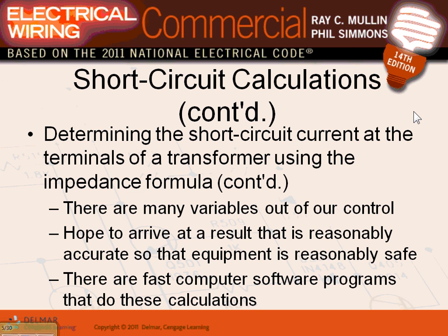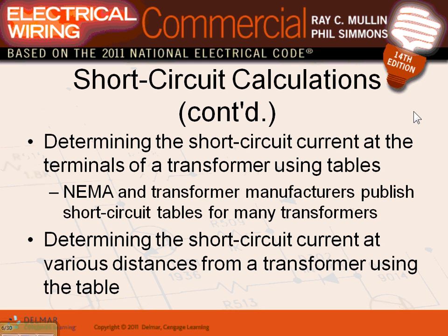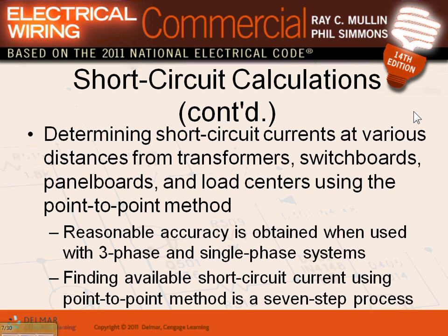Okay, arrive reasonable. This is all soft. Here's the key point. We always use software programs, PTW, more accurate. But your start point is going to be always the transformer. Transformers determine the short circuit current at various distances. So step number one, and I'm going to go all the way to the examples because it makes a lot of sense to do it.